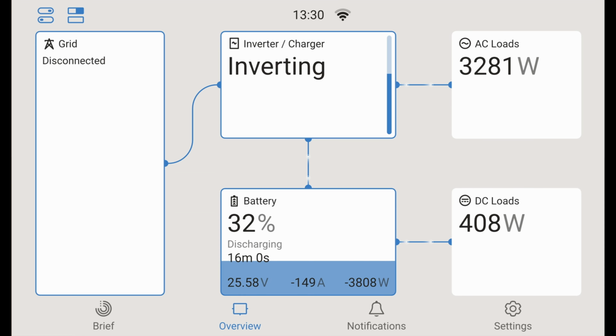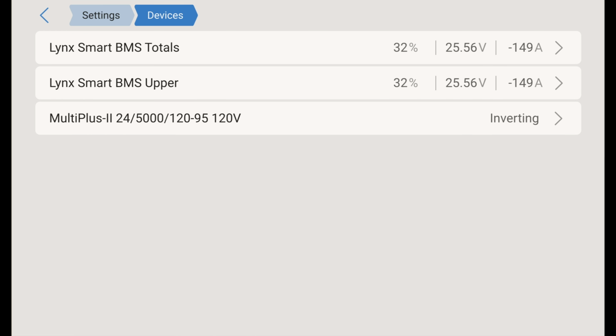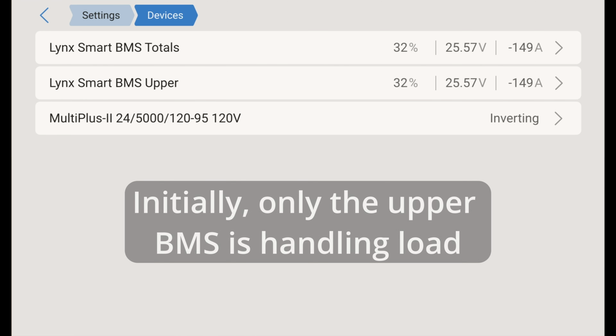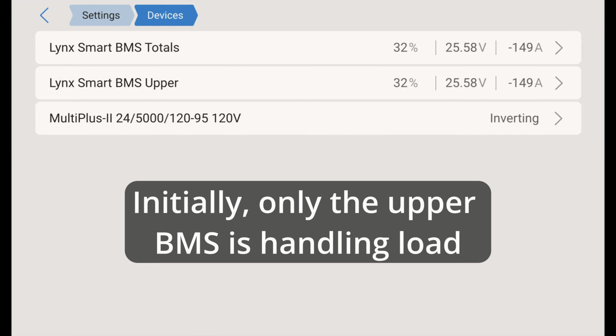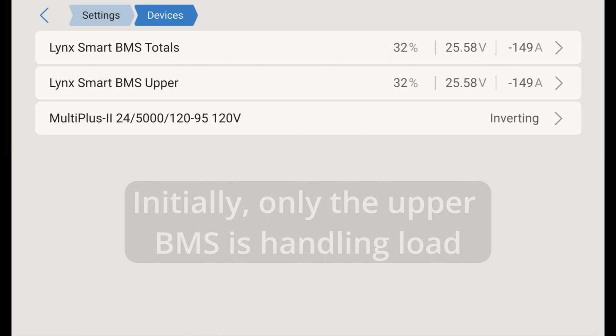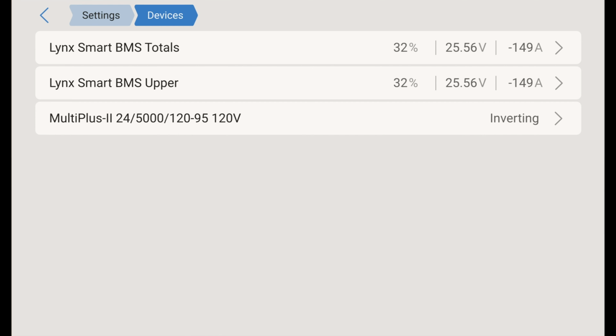Okay, so we're going to get our testing underway with about a 150 amp load on the batteries. Right now what we see is that only the upper BMS is showing, and then the totals, because the lower BMS is currently disabled or offline. In a minute we will go ahead and turn the lower BMS on.